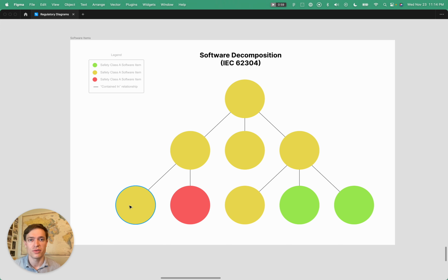If you have too much information, your model or your analysis is not going to help, because you'll be so overwhelmed with the amount of information. So we tend to like to start with a relatively rough decomposition, and then decompose it more in conjunction with our risk analysis. And if we feel like there are risks originating in one area, or also risk control measures that are implemented by a particular area, we'll split those out with more and more detail.